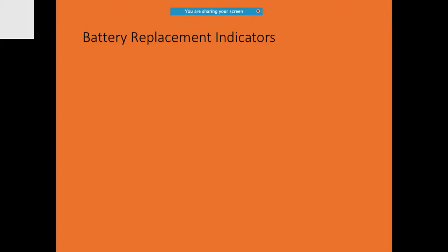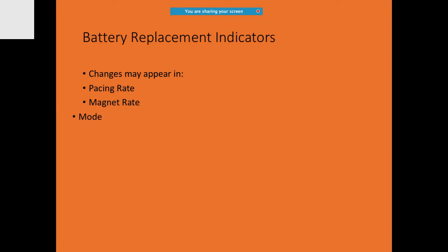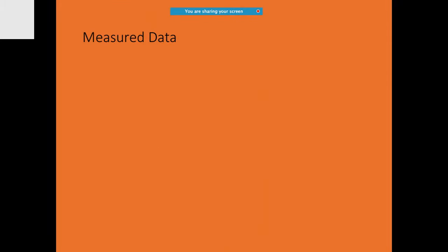Also, at what rate was pacing being done and at what output. So how do you distinguish about the replacement indicator — when do you think it can be replaced? You can know by the pacing rate, by seeing the mode, the magnet rate, and you can also see the pulse width or use data obtained through telemetry.